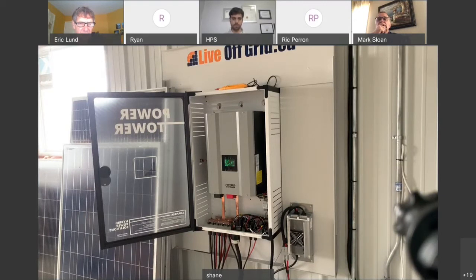For those who don't know what a rapid shutdown is, it's basically the same thing as a fireman switch system on a furnace. If there was ever a fire and the fireman had to show up, the first thing they usually do is cut a hole in the roof. Now if your panels are mounted there and they put a chainsaw through and hit 90 volts DC, there could be a complication. So what we want to do with the rapid shutdown is, when we lose our input or hit the fireman switch, we bring those modules down to their lowest open circuit level.